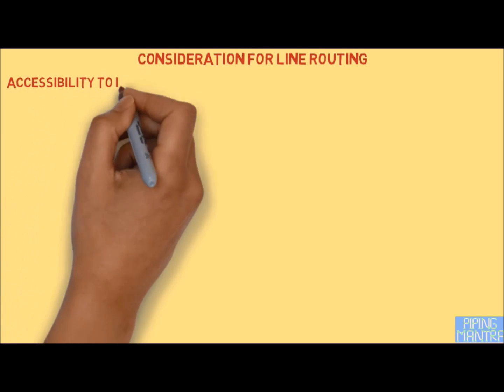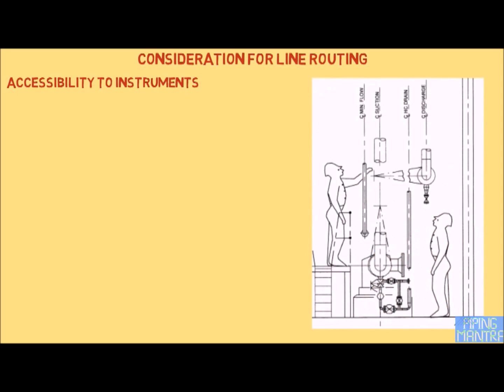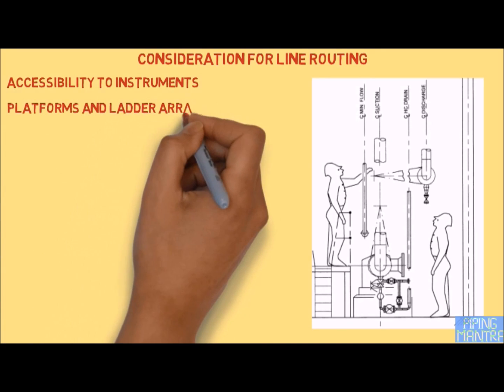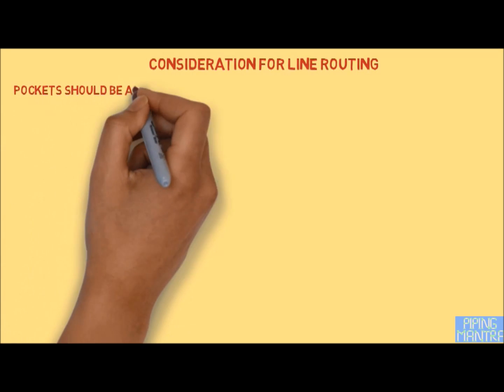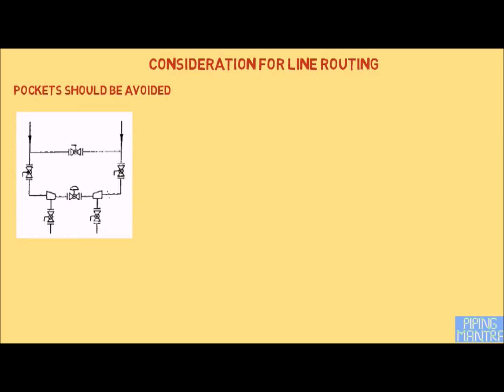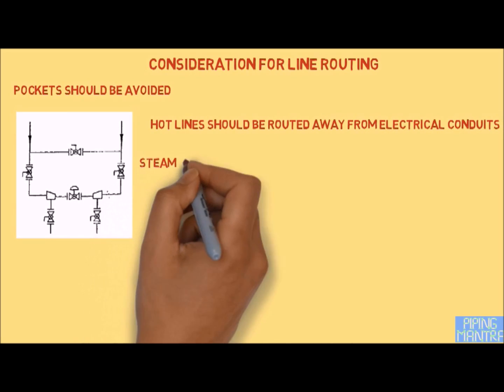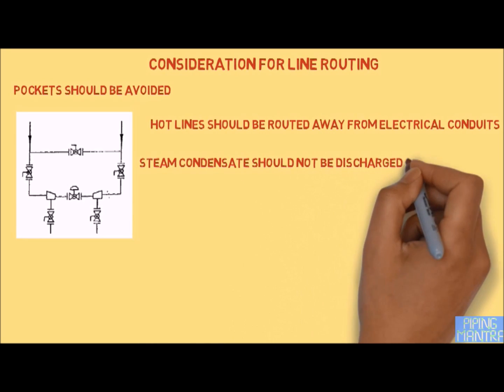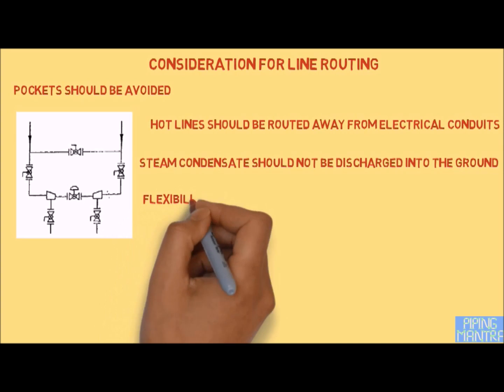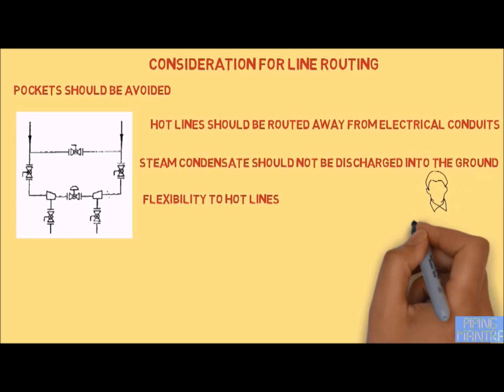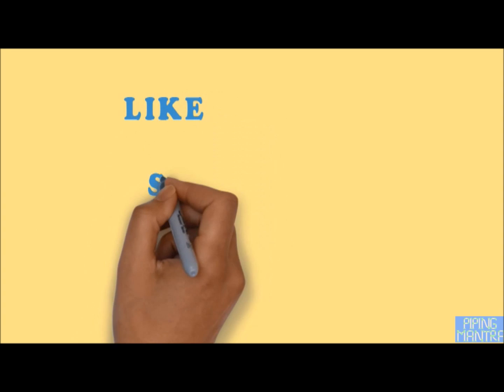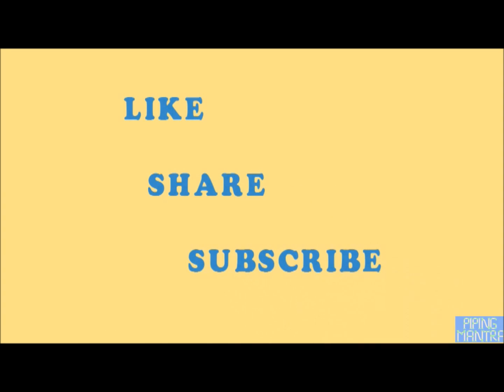All instruments — whether inline or online — and control valves should be readily accessible from grade level or from a permanent platform. Adequate platform and ladder arrangements should be provided for column manways. Piping pockets should be avoided unless specified. Hot lines should be routed away from electrical conduits, and steam condensate should not be discharged into the ground in the vicinity of electrical conduits. Hot lines should be routed with flexibility in concurrence with the stress engineer. Sample point piping should be as short as possible.